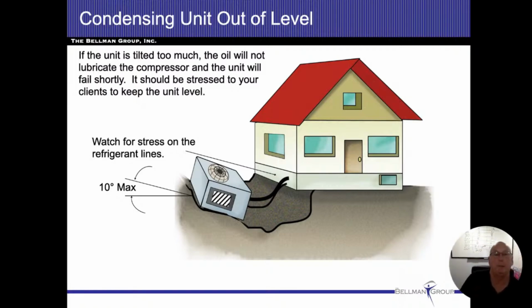So I know there's test questions about compressor cabinets being level, all right? In all reality, yeah, they should be level. I really don't make a big deal when they're not. This slide is telling us we can go all the way up to 10 degrees, and it's not going to be that much of a big deal. But if it was a piston compressor, the whole purpose for this levelness is that the motors that are spinning need to have oil to keep them lubricated. And if they're not lubricated, or the oil's not getting to them, then the motors are going to seize, and then obviously the air conditioner is going to be damaged.